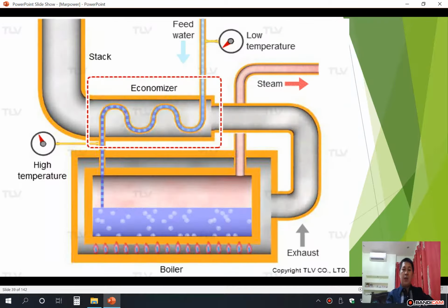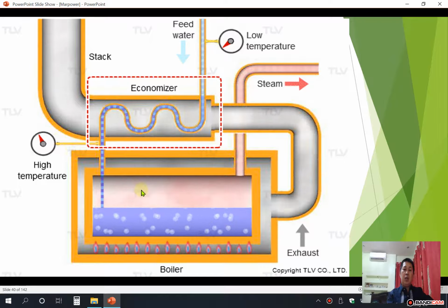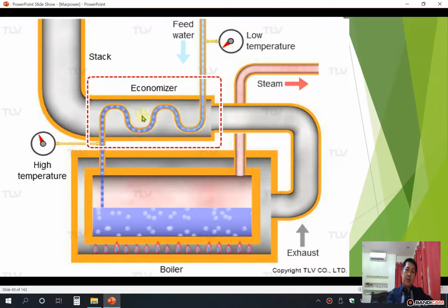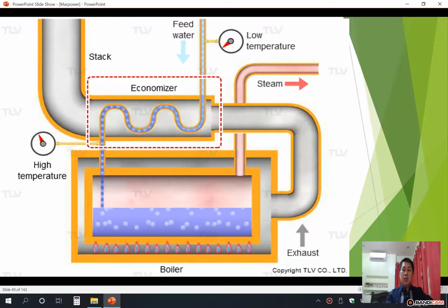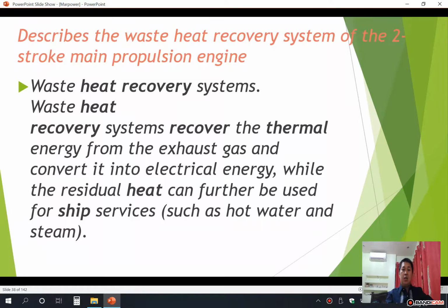Here you see you have exhaust gas flowing, and there is a flow of boiler water here. Your boiler water is boiling and generating steam. You see here the boiler water is at low temperature, and when already heated here, it becomes high temperature and produces steam. So this is the exhaust gas heat recovery system. So, waste heat.